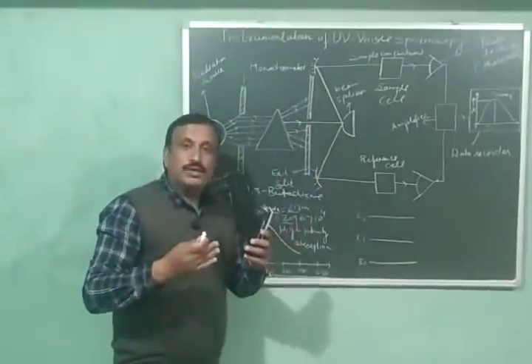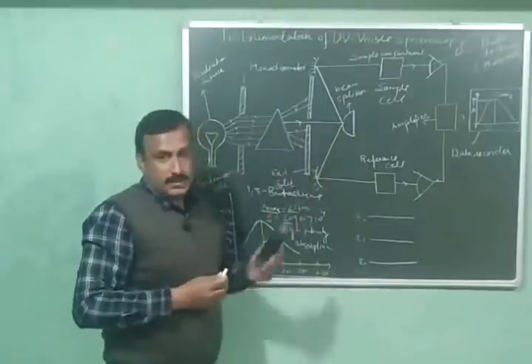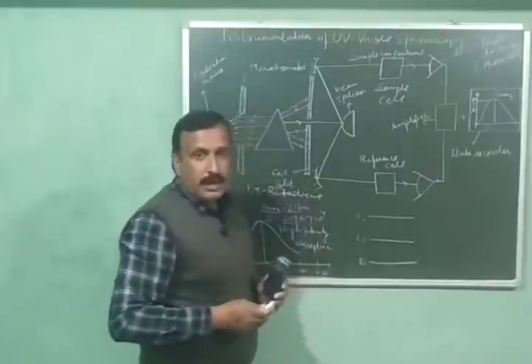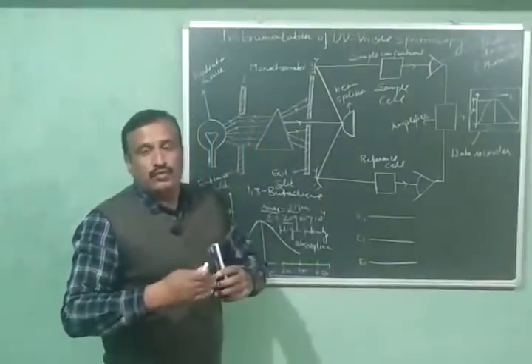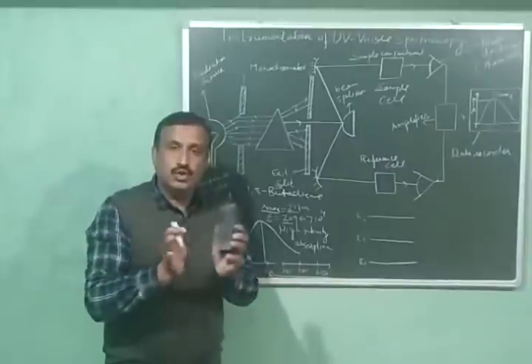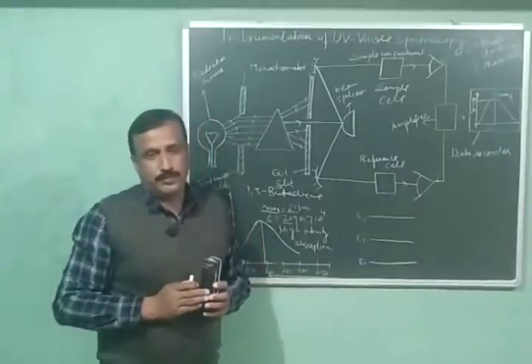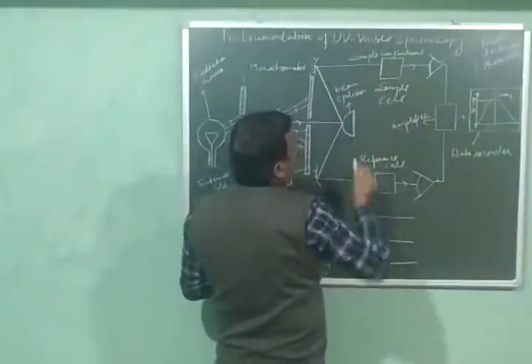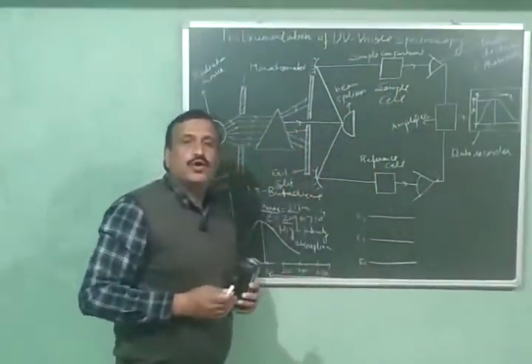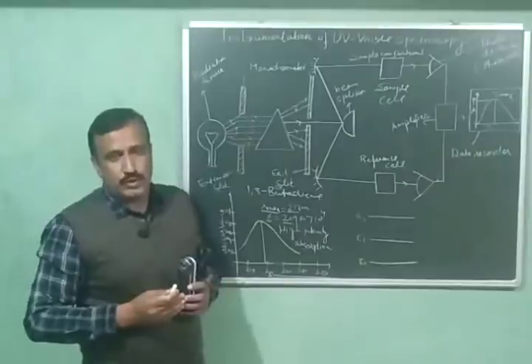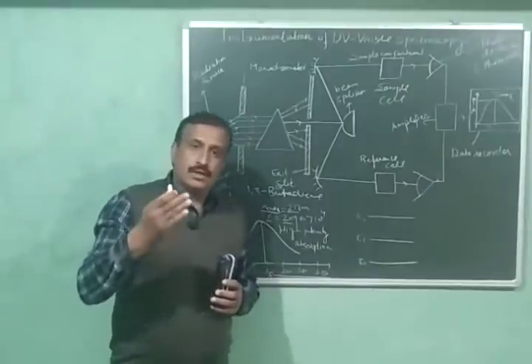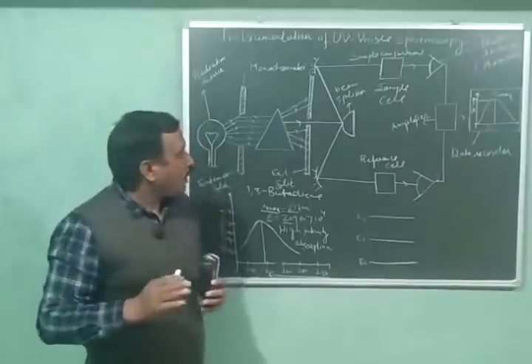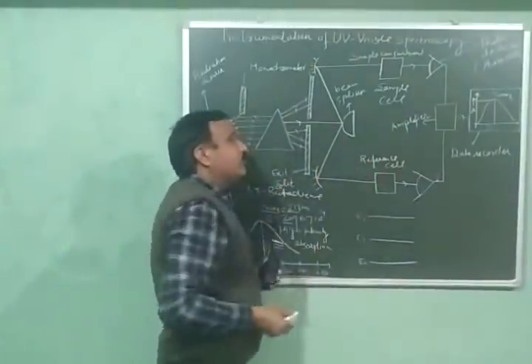Only one wavelength is selected from the exit slit. That radiation is allowed to fall on the beam splitter, which splits it into two beams of equal intensity. The first beam is passed through the sample cell, containing a solution of the sample in a suitable solvent — the compound whose UV-visible spectrum we want to study.